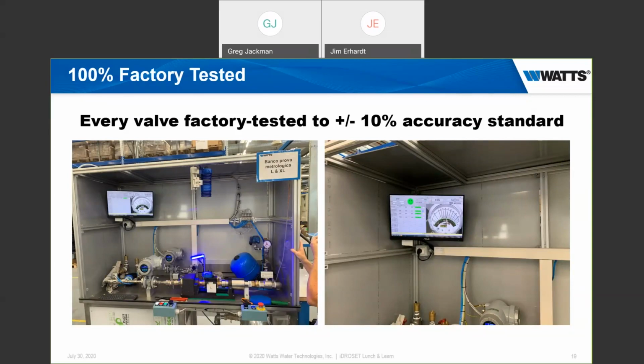The iDROSET reads the flow directly. It's a flow meter as opposed to taking a pressure differential reading and then calculating what the flow might be based on a CV number or the resistance inside the valve. To that point, these valves are manufactured in our factory in Italy. Every single valve, before it gets packed, goes on the test stand that you see right here. On the left side, you'll see the entire test stand with all calibrated instruments.